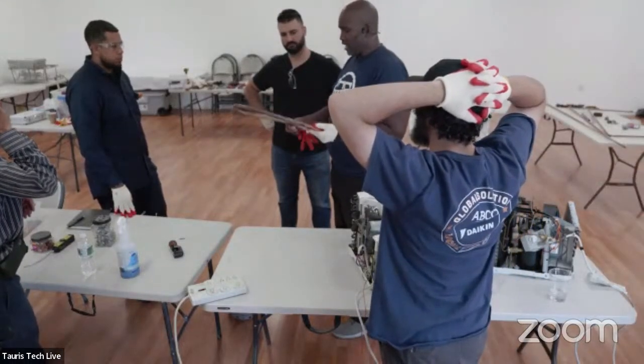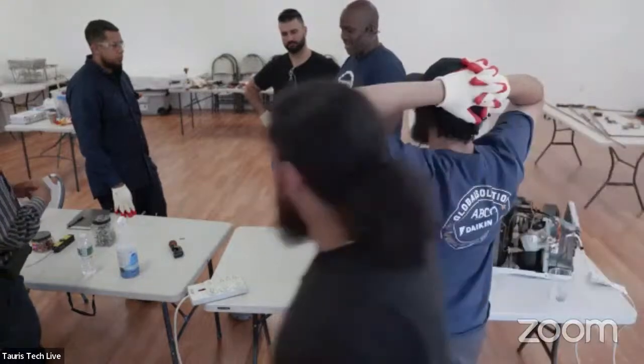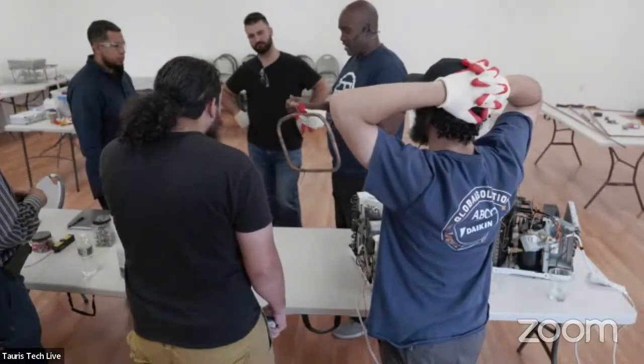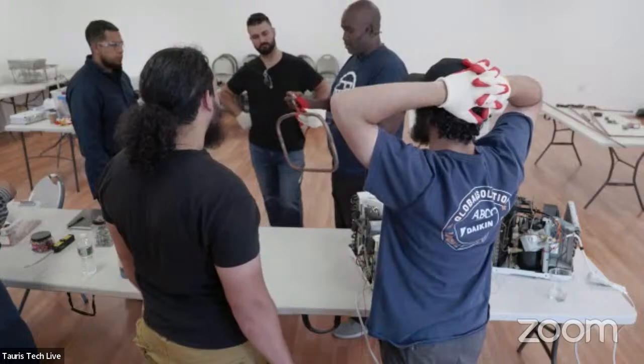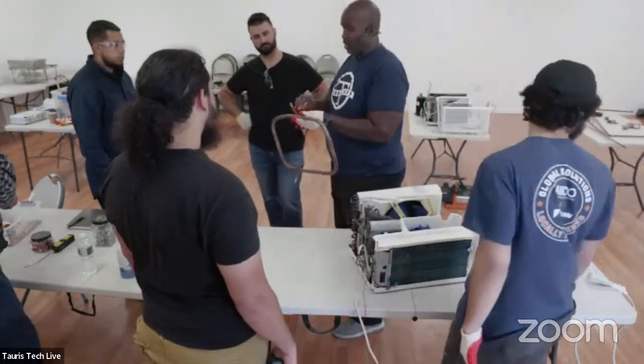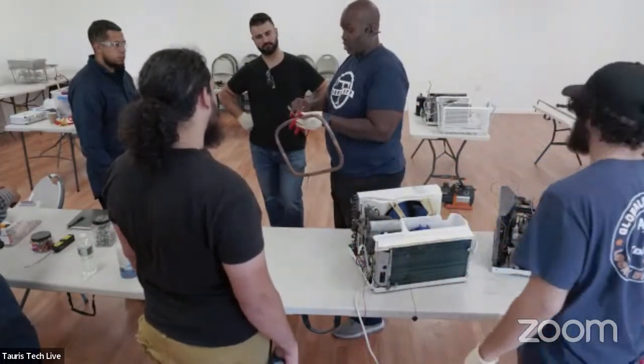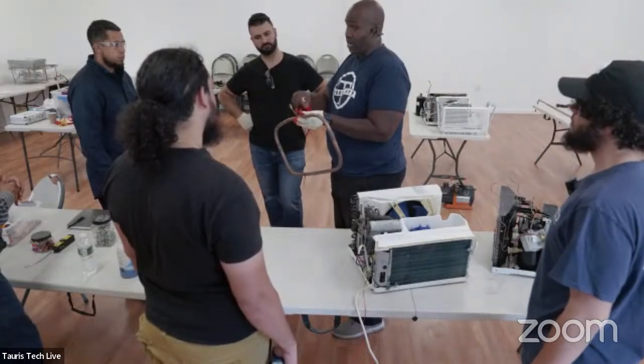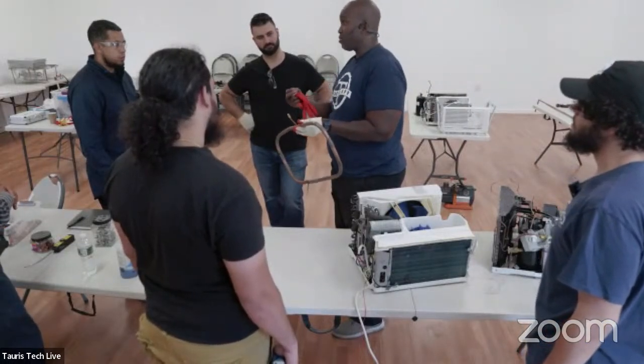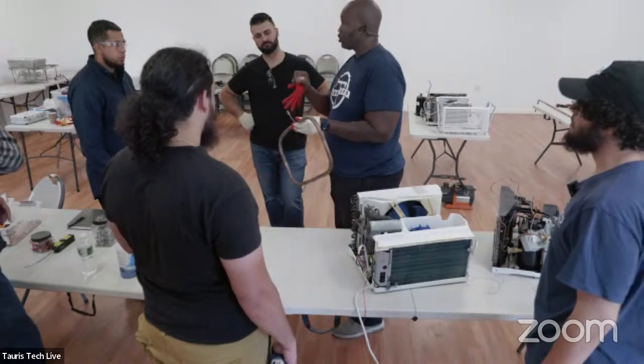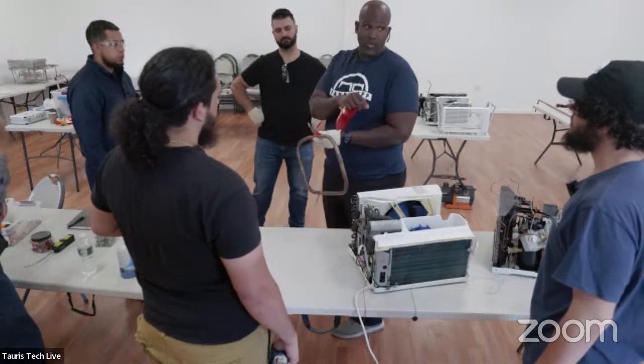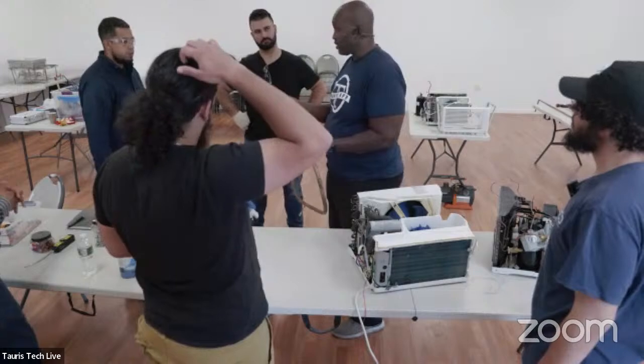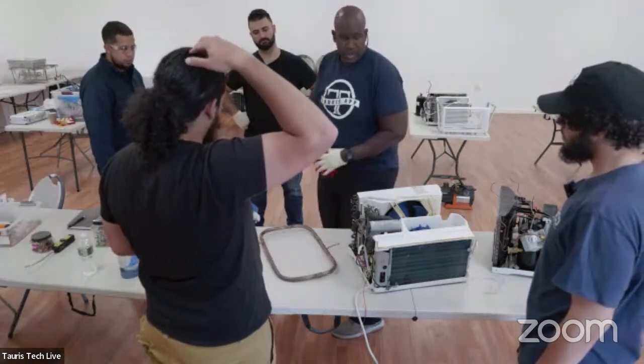So we're gonna make something kind of like a pipe bomb, I guess. We're gonna take some plumbing pipe, cut the ends, put the caps on the ends, braze those on. You're gonna have to drill a hole, cut this off, and we'll put that in the hole and braze it on there, then we'll do pressure tests to see if it holds. So we charge nitrogen in it, put it into water, see if there's any bubbles, to check the pressure. So, cutting.